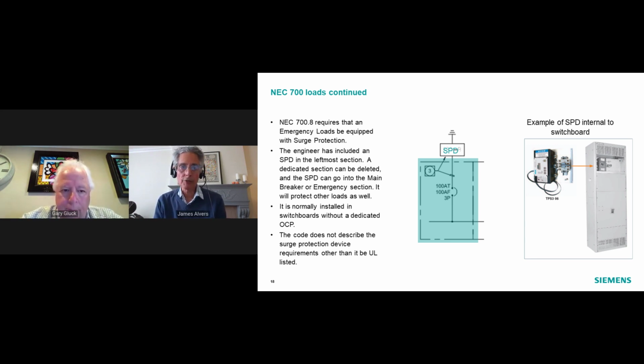So NEC 700.8 requires that emergency loads be equipped with surge protection. The engineer has included this in the leftmost section, and it's a separate section. This dedicated section can probably be deleted. Most manufacturers don't require a separate overcurrent protection device. It's included in the SPD. And for instance, here's an example of a section with a main breaker with the SPD mounted above the main breaker in a compartment. And it would serve the whole board. And that's fairly typical for all switchboard providers.